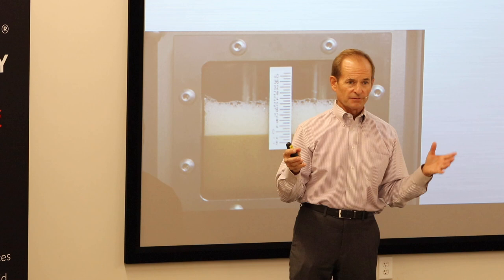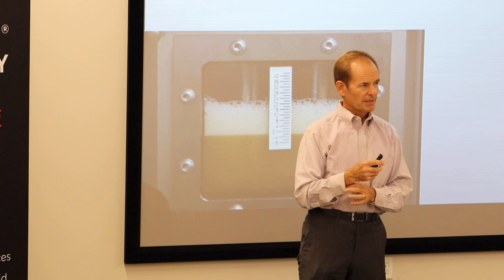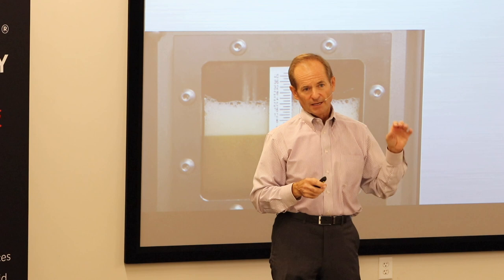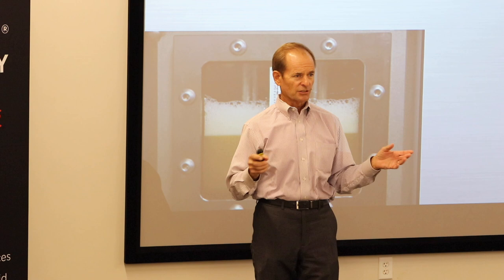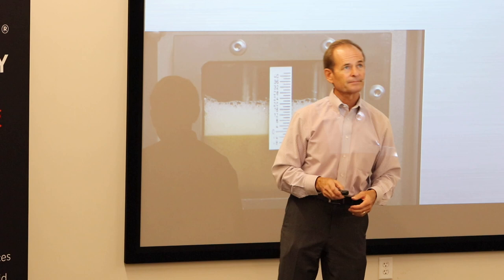Anti-foam additives are actually in many, many industrial oils — and many non-industrial lubricants have anti-foam additive as well. Anti-foam additive can be treated at very tiny rates — these things are in the 10 parts per million range. You just need a whiff of it in there and they can be pretty effective.